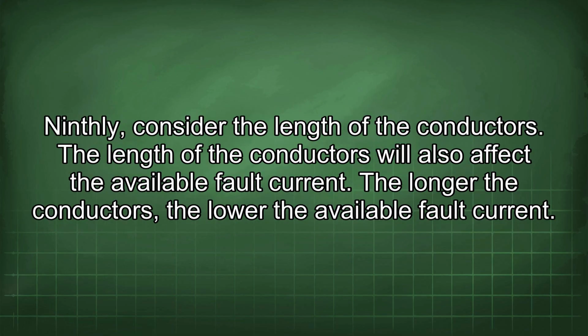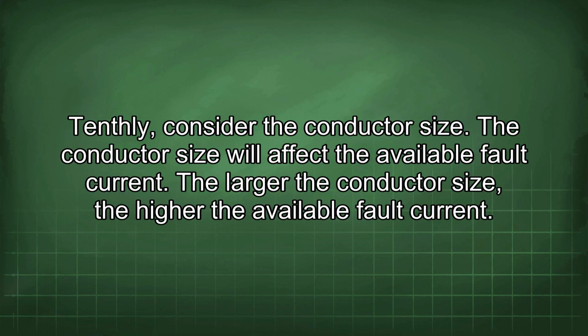Ninthly, consider the length of the conductors. The length of the conductors will also affect the available fault current. The longer the conductors, the lower the available fault current. Tenthly, consider the conductor size. The conductor size will affect the available fault current. The larger the conductor size, the higher the available fault current.